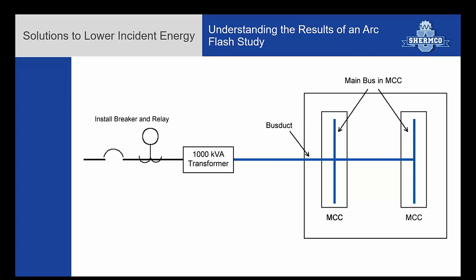And sometimes what we found is that we can actually put the relay in here on the secondary. Sometimes we can't see through the transformer and detect arcing current well enough on 480. So sometimes we might actually put this relay right at the secondary terminals, the CTs, and then go back up and trip this main breaker. This is typically more economical because you're not dealing with the high ampacity bus on the low side. You're typically dealing with medium voltage cables, and you can get a breaker or trippable switch to fit in the same place as existing equipment.